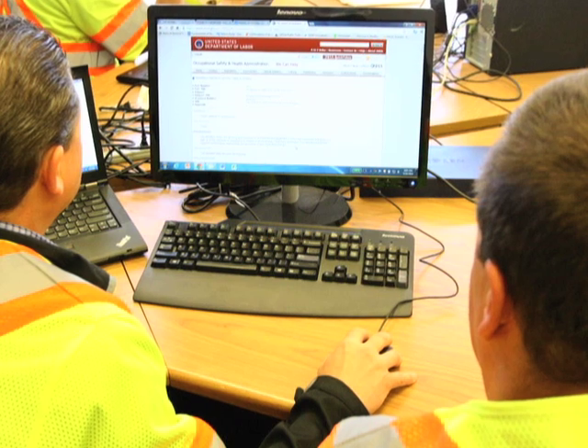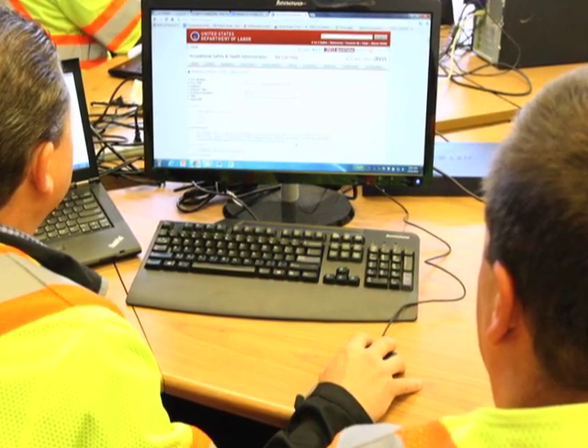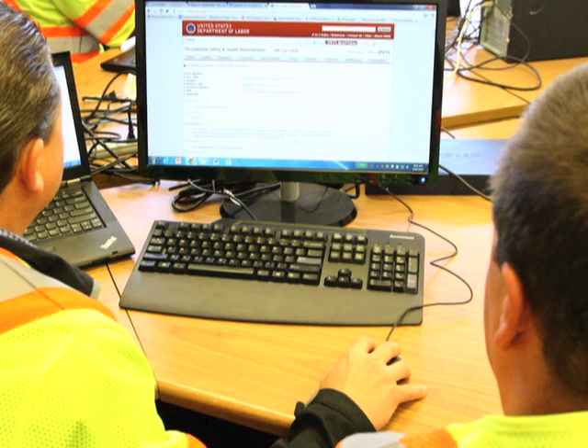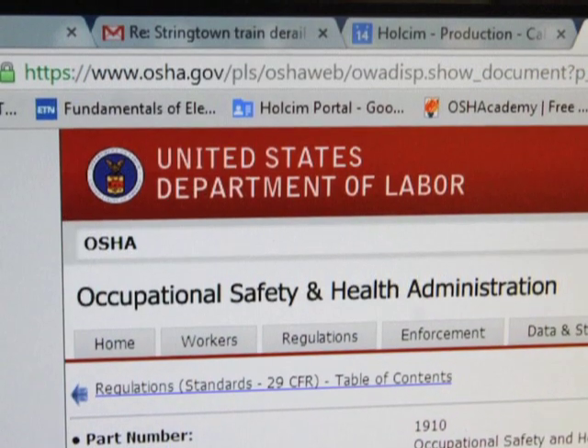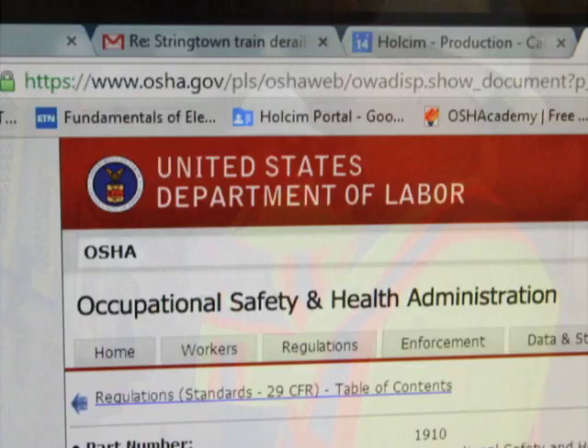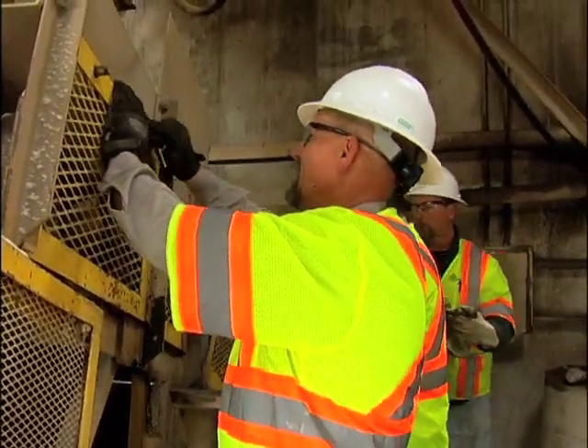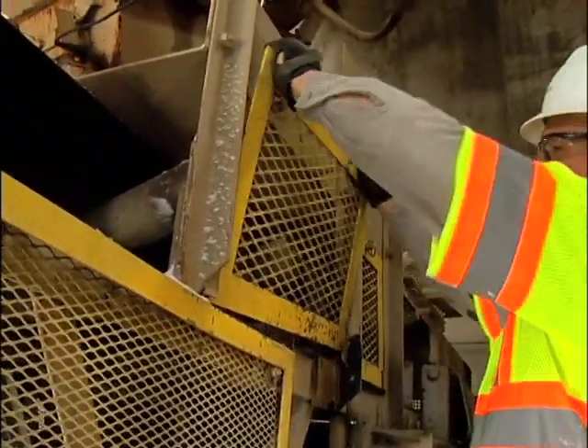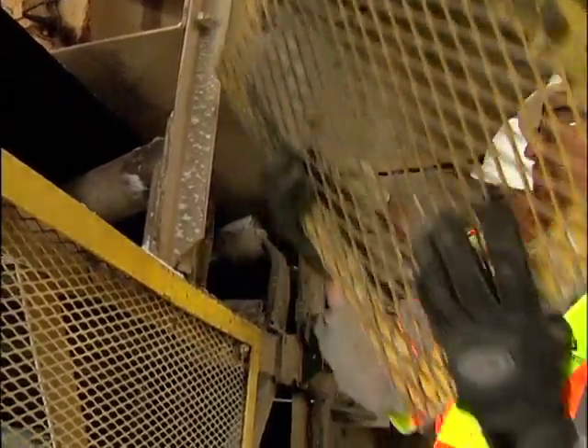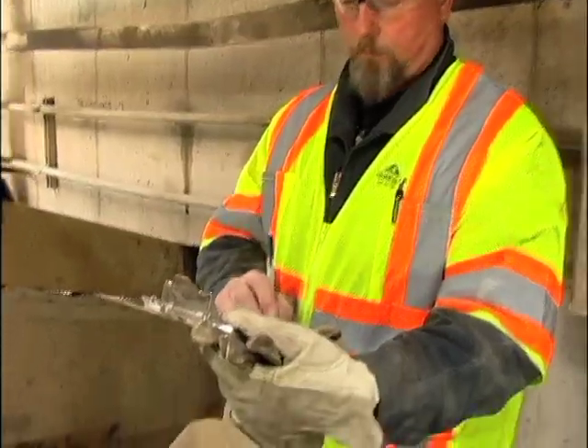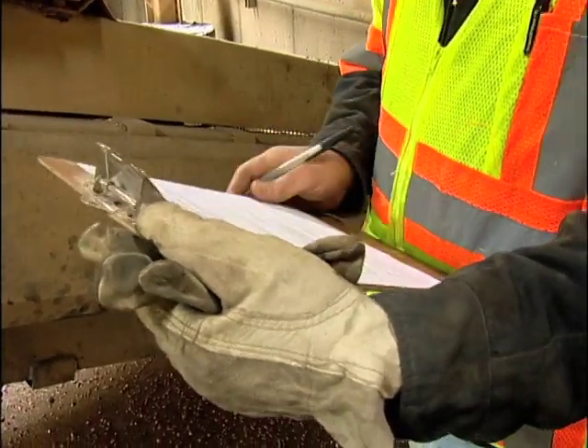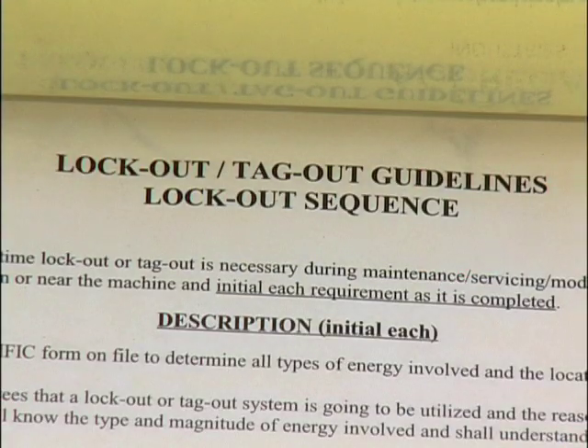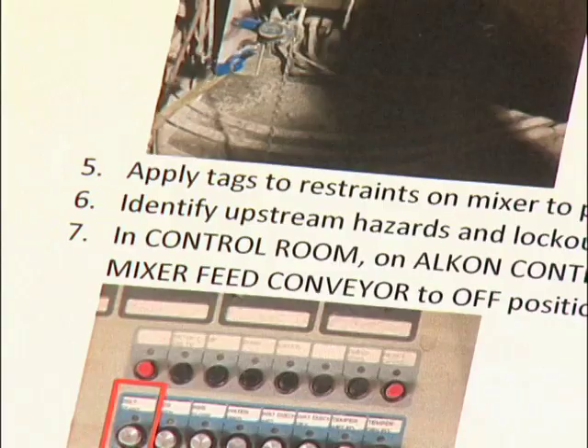Compliance with OSHA Standard 29 CFR 1910 1910.147 is mandatory at ready-mix concrete plants. Compliance is not optional. The law covers the servicing and maintaining of plant machines and equipment in which unexpected energization or startup of the machines or equipment or release of stored energy can cause accidents and injuries. Parts of the OSHA standard require employers to establish a program with specific lockout, tagout, and tryout procedures for all energized equipment at a ready-mix concrete plant.